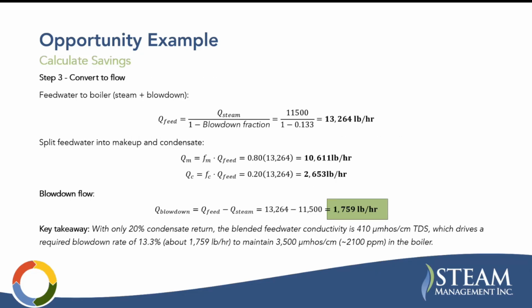So we can convert that to a blowdown flow, essentially is what we're doing here. You're taking the steam flow. That percentage is a percentage of feed water, so you kind of have to flip the percentage from feed water and use your steam flow. In the end, this is your feed water flow that you're determining based on that blowdown percentage. You can use that with your condensate and makeup water percentages to determine those. But in the end, what we're concerned about is this blowdown flow. So this is your energy stream, 1,759 pounds per hour of saturated liquid at 100 pounds. And that's a pretty significant energy stream, relatively speaking.